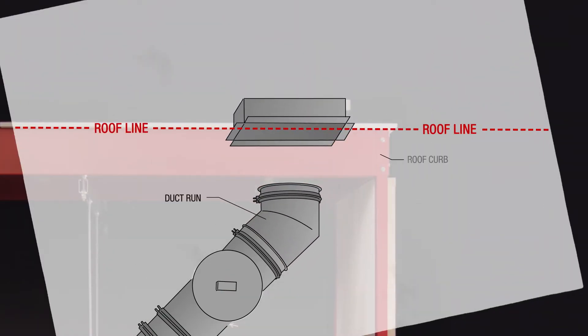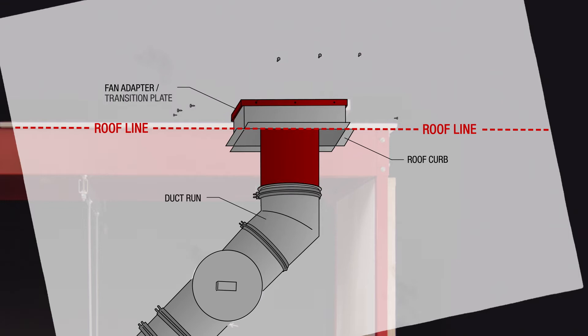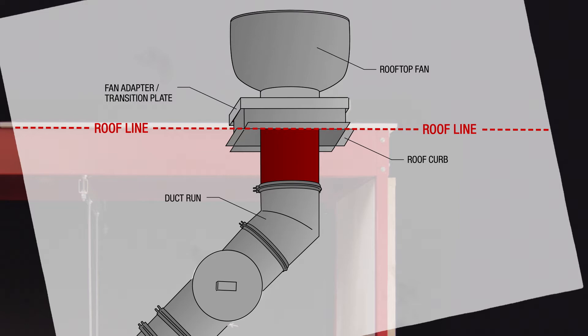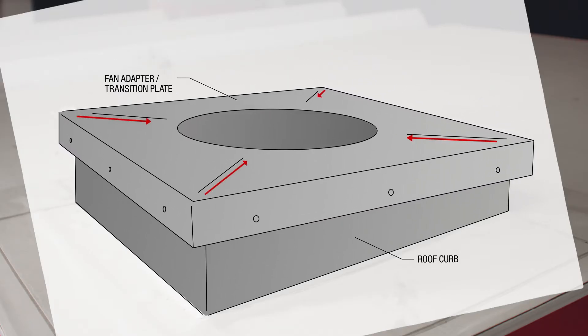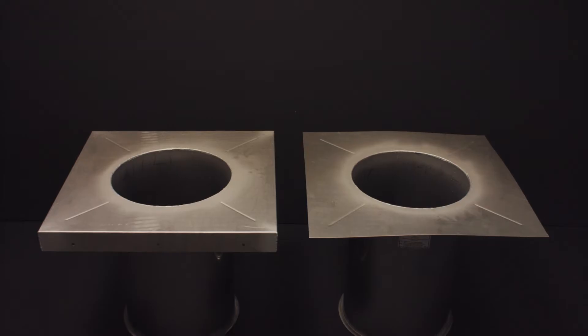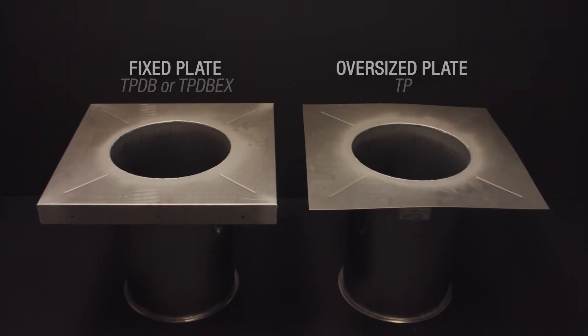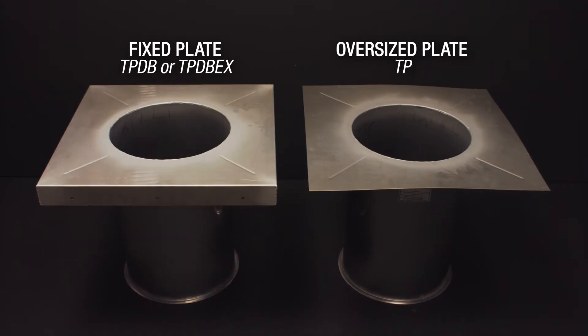The fan adapter plate, or transition plate, is designed to connect to a previously installed roof curb. When connected, the plate mounts on top of the fan curb, which supports the fan housing. The adapter plate is formed to provide a slope, allowing grease deposits to flow back into the duct. There are two categories of transition plates, either fixed or oversized.